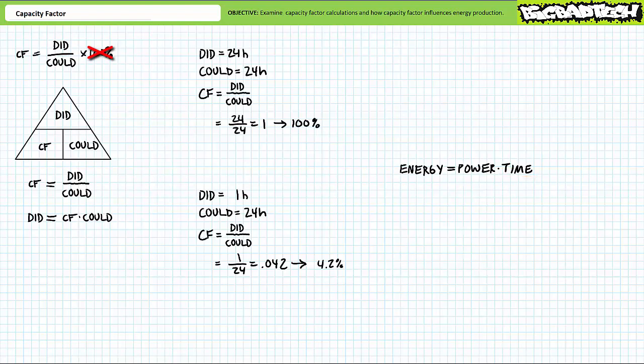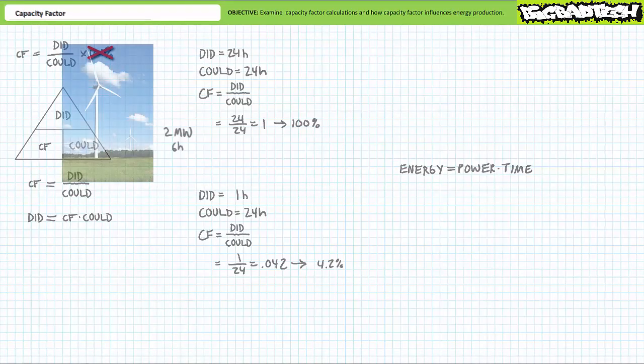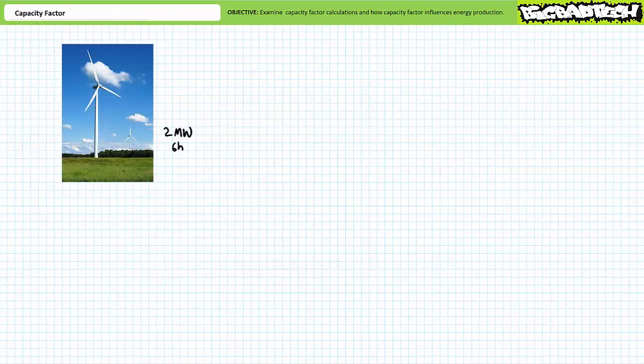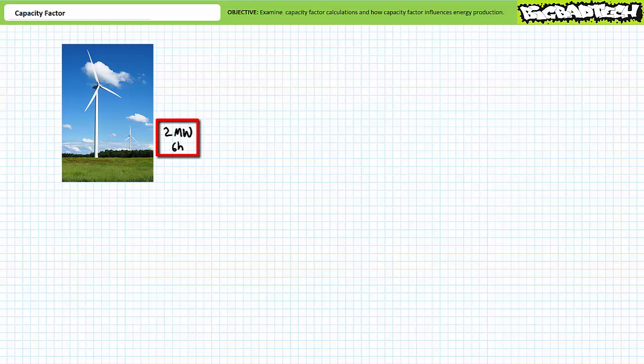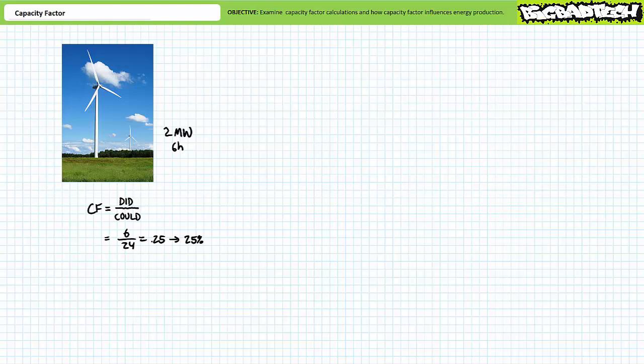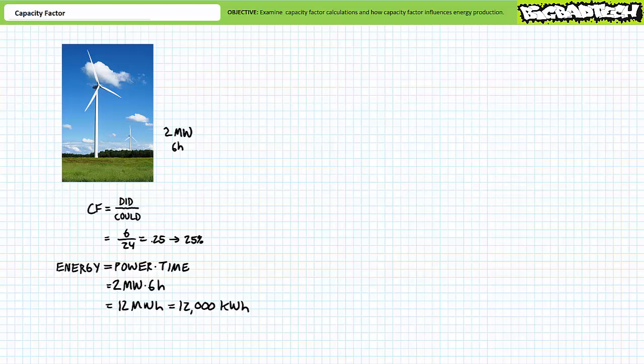Let's try a couple of illustrated examples of simple capacity factor calculations. Consider an industrial wind turbine. As you're no doubt aware, some days it's windy and some days it isn't. Let's say this is a 2 megawatt wind turbine that typically operates at full capacity for only 6 hours a day. The capacity factor for this turbine is did over could or 6 over 24 or 25%. If energy is power times time on a typical day, this turbine would be expected to produce 2 megawatts times 6 hours or 12 megawatt hours or 12,000 kilowatt hours of energy.